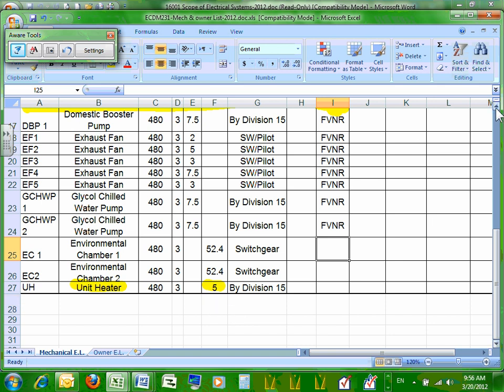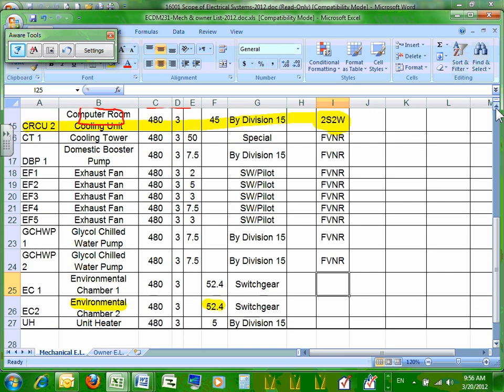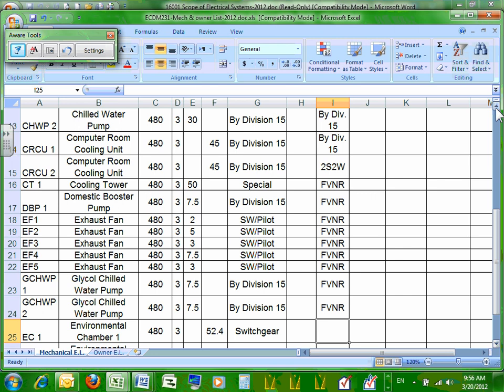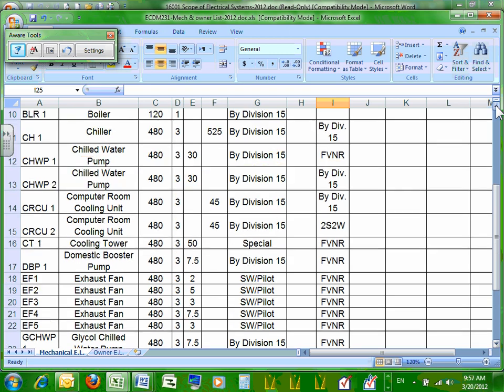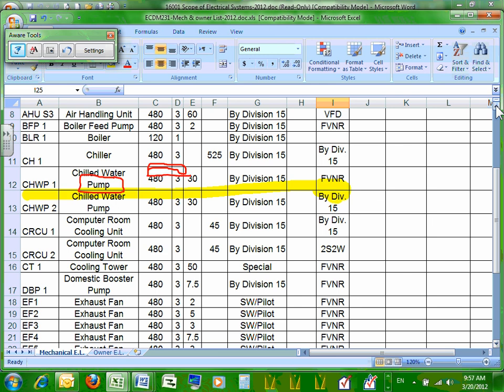And maybe what I could have put in to make that more challenging is, as part of my air handler, I could have had a supply return fan, and I could have said I'm assuming we're getting natural gas, since I didn't focus on how we're getting heat here. To make this more complicated, I could have said I have a 50, 60 kW or 100 kW heating element as electric heat. But that's not in here, and at the moment I'm not changing that. And these are year round. Those CRAC units, that 150 watts a square foot, when we get there, that's constant.